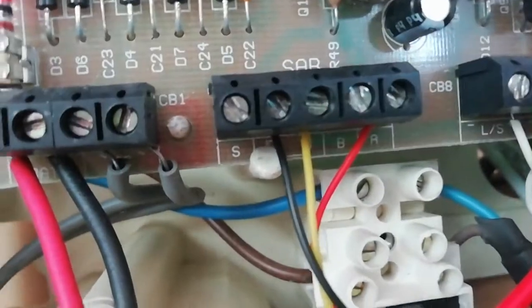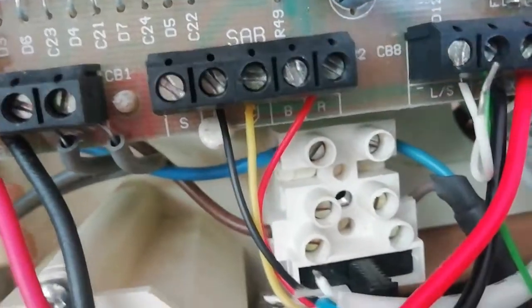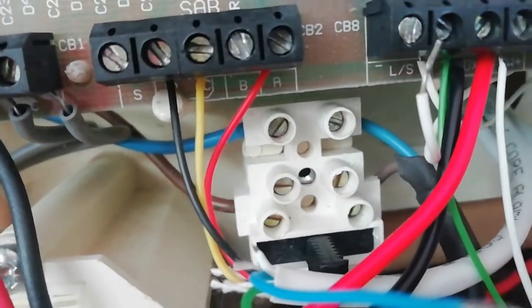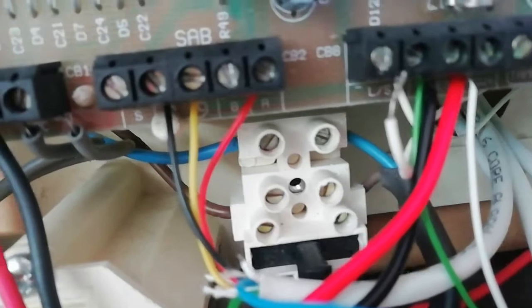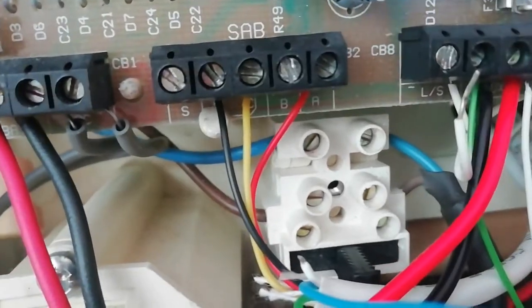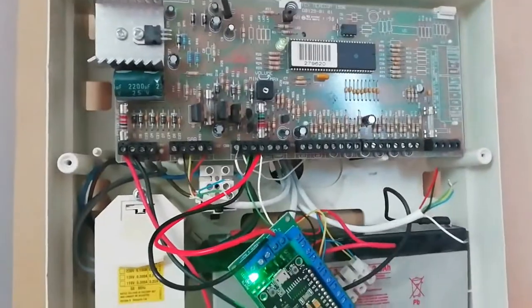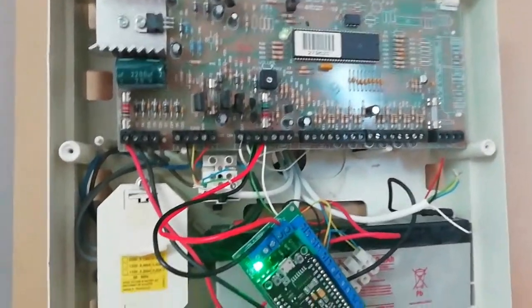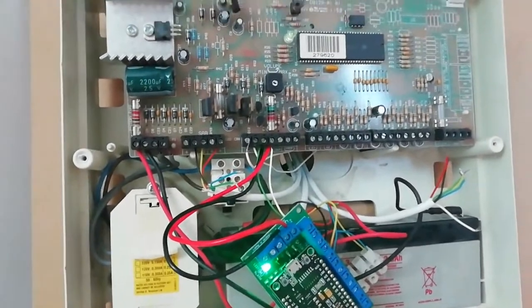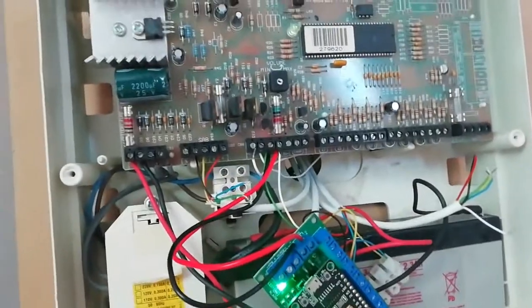We downloaded the manual for this particular model and it told us that the S terminal and the B terminal are the switched negative terminals for strobe and bell.